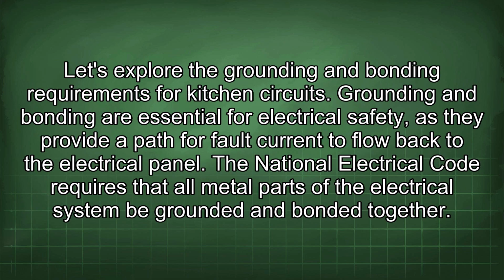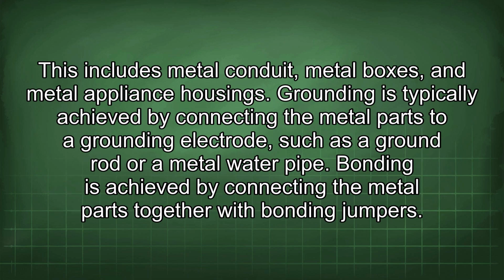Let's explore the grounding and bonding requirements for kitchen circuits. Grounding and bonding are essential for electrical safety, as they provide a path for fault current to flow back to the electrical panel. The National Electrical Code requires that all metal parts of the electrical system be grounded and bonded together. This includes metal conduit, metal boxes, and metal appliance housings.